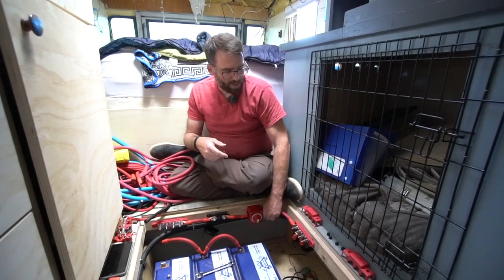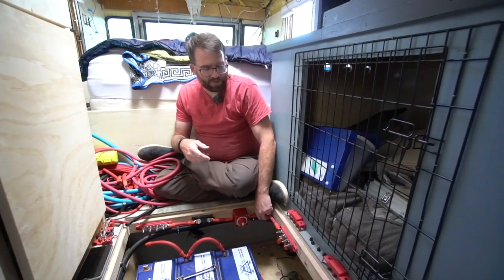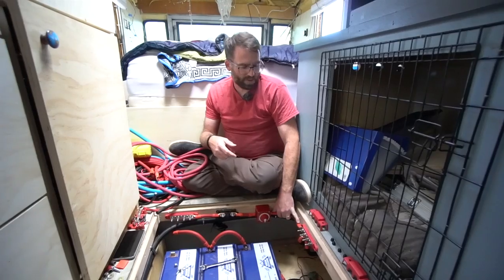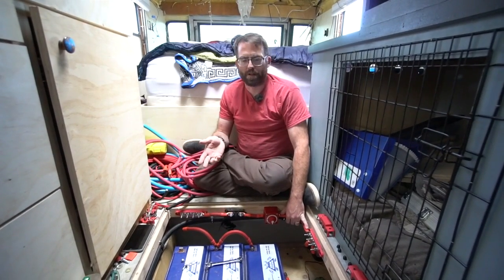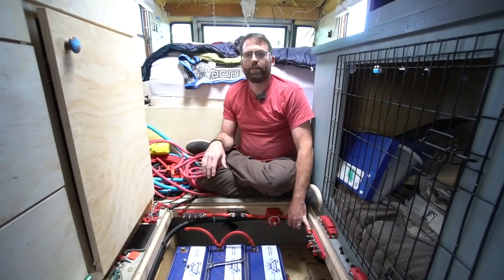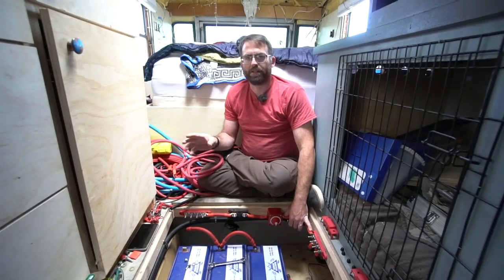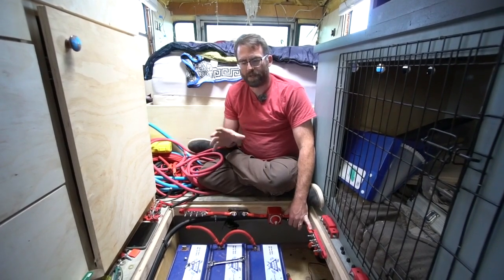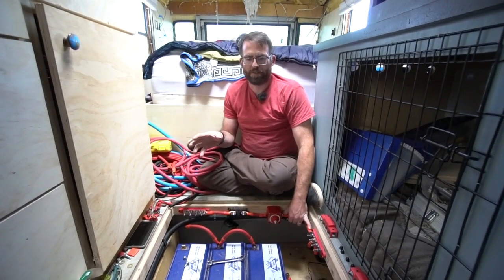I need to still do the load calc math on this. I think 2-gauge is going to be totally fine, especially this run that's literally 10 inches long. But for every length of wire that you're putting in here, you need to either protect it and calculate that you're not overloading the wire for the size that you've got.